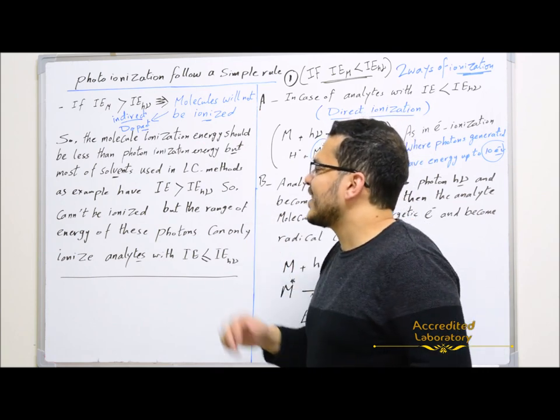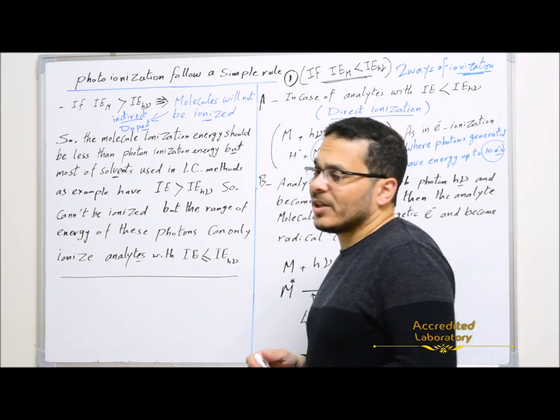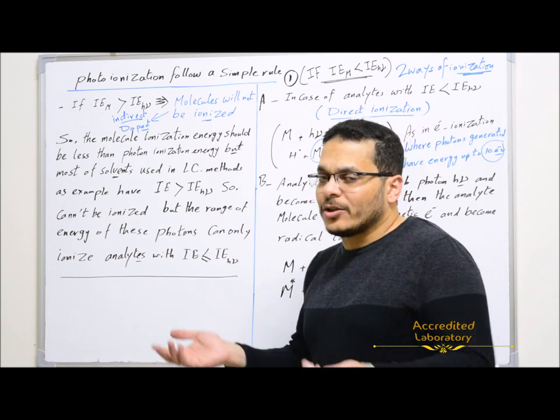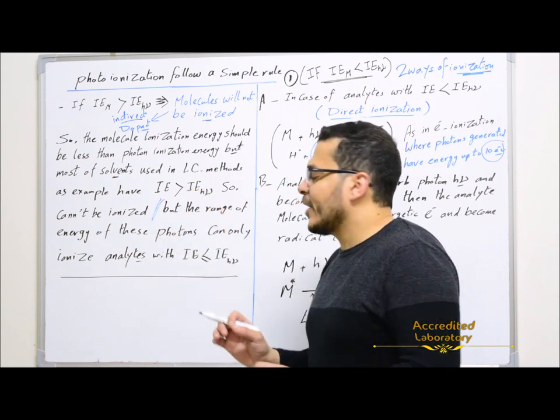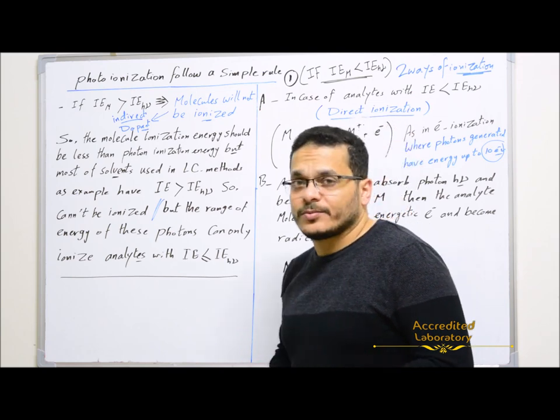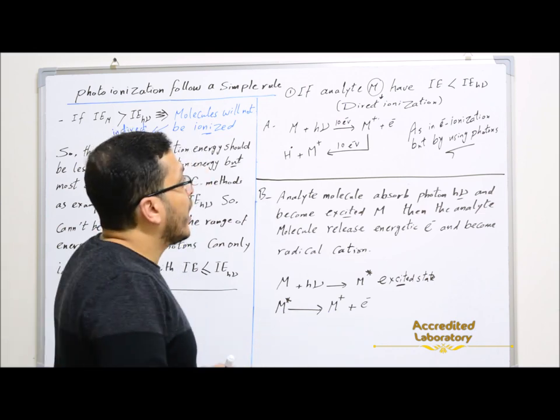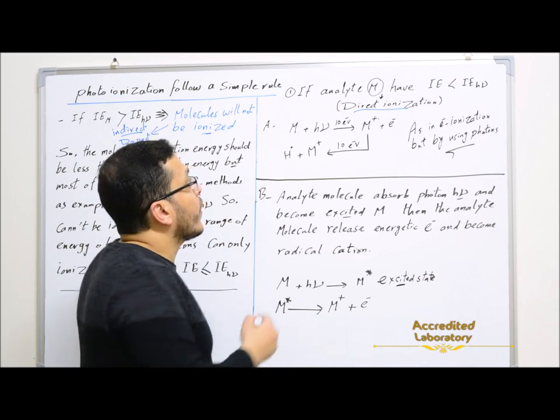The molecule ionization energy should be less than the photon ionization energy. For solvents, most solvents used in LC-MS methods have ionization energy higher than the ionization energy of photons, so they cannot be ionized by the photons. The range of energy of these photons can only ionize analytes with ionization energy lower than the ionization energy of the photons. If the analyte molecules have ionization energy lower than the ionization energy of the photons, there will be no problem and there will be direct ionization — the analyte molecules will be ionized by the photons.